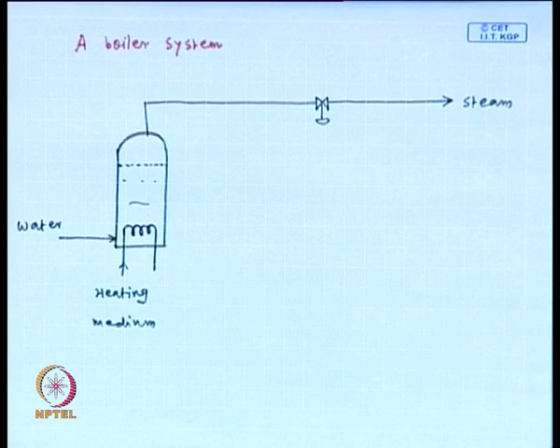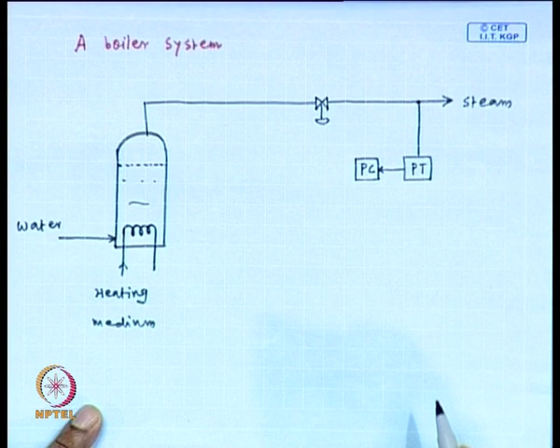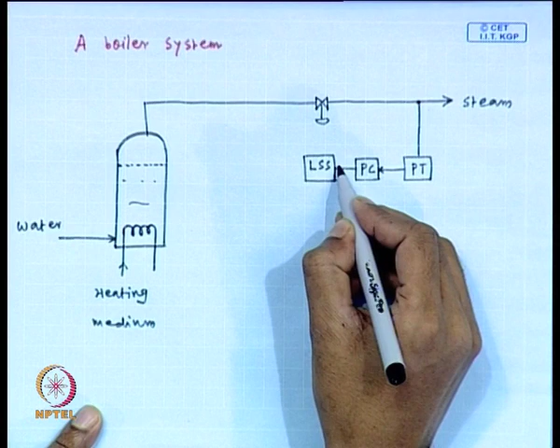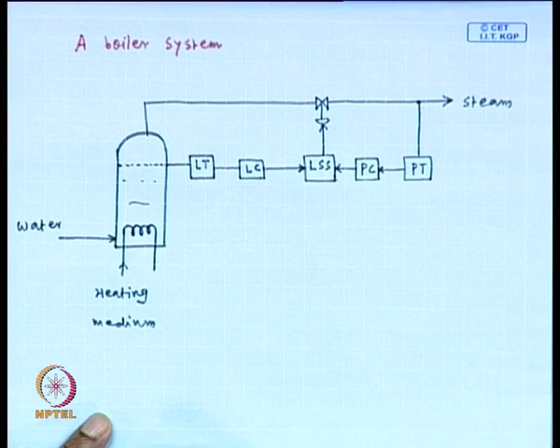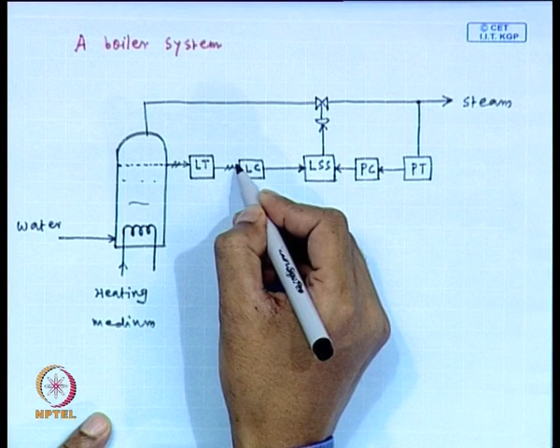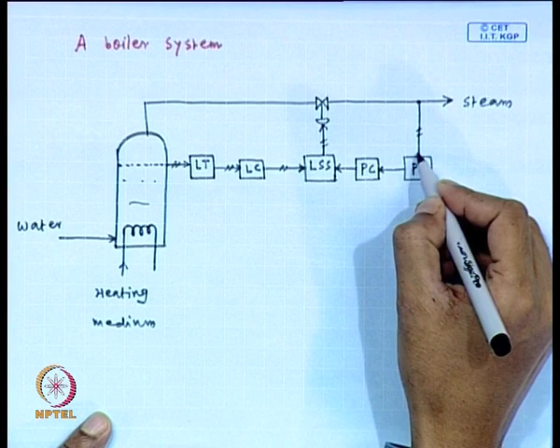Now, we wish to include the control scheme. So, first a pressure transmitter is employed to measure the steam pressure, then a pressure controller, and here we use one switch, that is LSS. We will discuss why we have selected LSS. Another control scheme is also employed to maintain the liquid level. For that we need to employ one level measuring device, that is LT, then one level controller, then the controller signal goes to LSS. LSS output is implemented through the control valve. Fine. This is the constraint control for a boiler system.